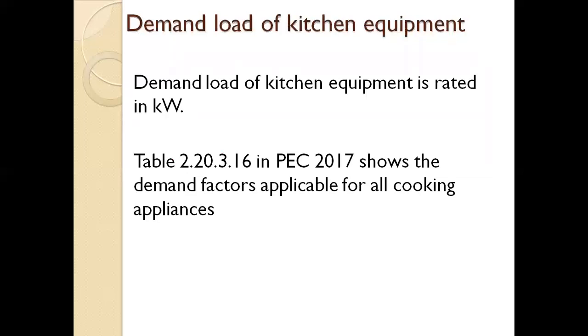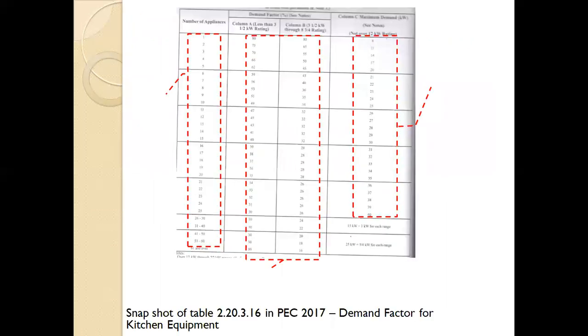So, demand load of kitchen. Table 2.20.3.16 gives the demand factors applicable for all cooking appliances. As you can see, this is a snapshot of Table 2.20.3.16 of the PEC. On the inner left side is the number of appliances. Next is column A, less than 3 kilowatt or 3.5 kilowatt rating, and column B is 3.5 kilowatt up to 8.75 kilowatt rating. Column C is the maximum demand in terms of kilowatt, not over 12 kilowatt rating. There are also notes.